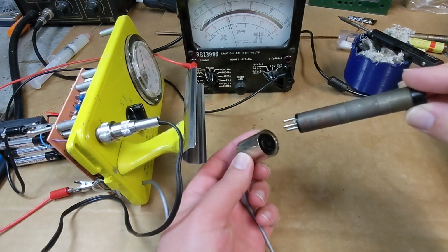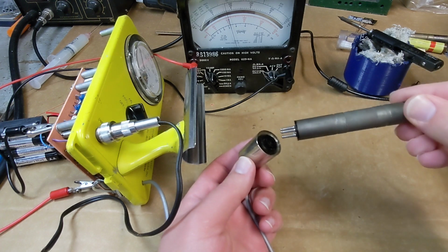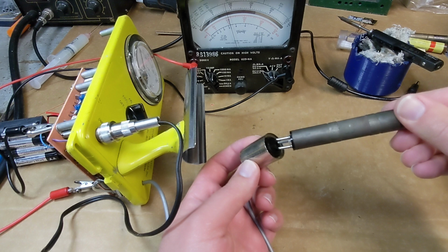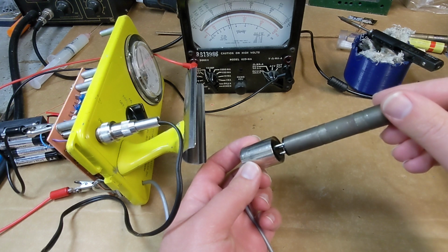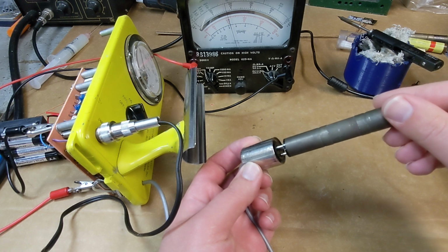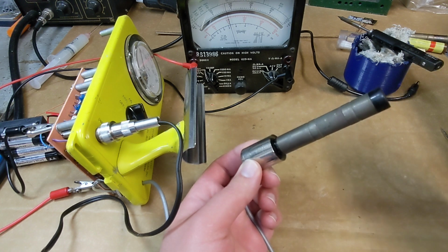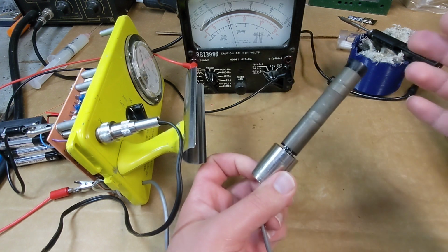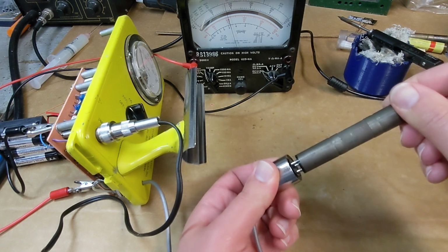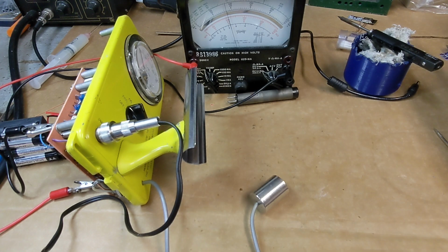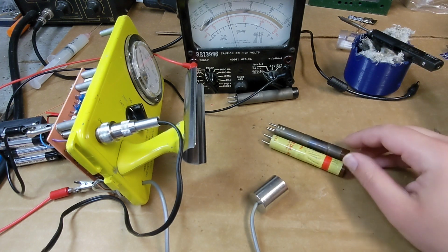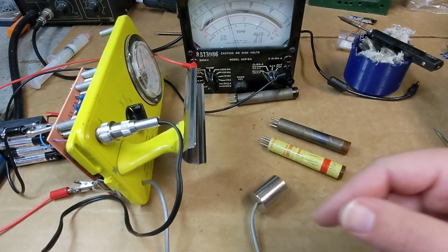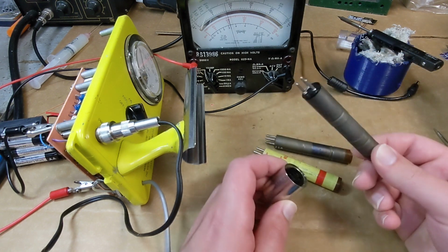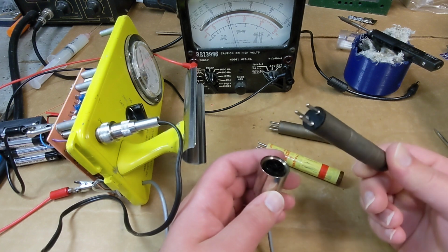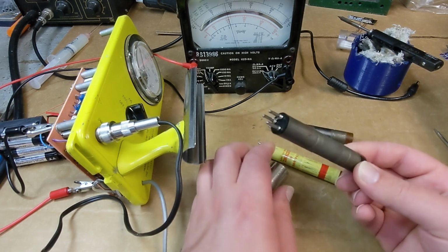If I take this bad tube, or that I suspect to be bad, and just touch it in there, as I insert and remove it, you can hear it clicking, but once it's all in, nothing happens. So this may very well be a shorted tube. Now I do have 2 tubes here that are supposed to be good, but the other thing about these is, well, a Geiger tube is a 2-terminal device, but there's 3 pins on here.